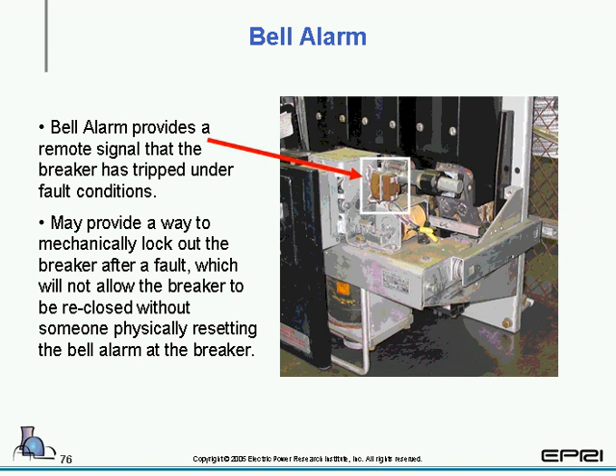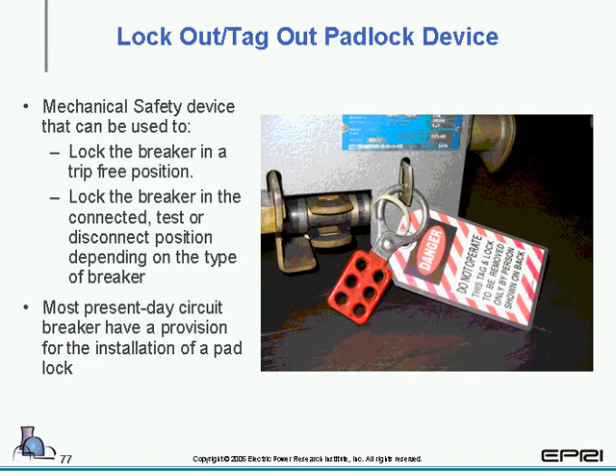Bell alarms. Bell alarms provide a remote signal that the breaker has tripped under fault conditions. They may also provide a mechanical lockout, which will not allow the breaker to reclose without someone physically going down and resetting that particular lockout. So when you look at a bell alarm, you may find that it's called a lockout or a bell alarm, or both. It could be a bell alarm and a lockout, or one or the other.